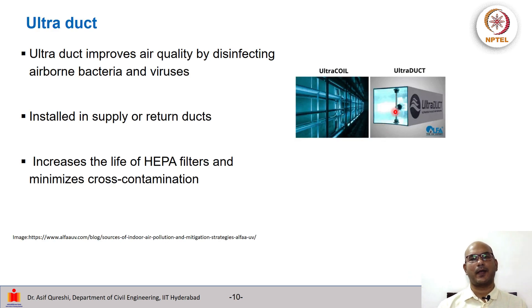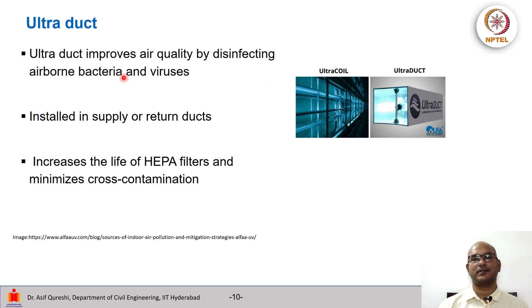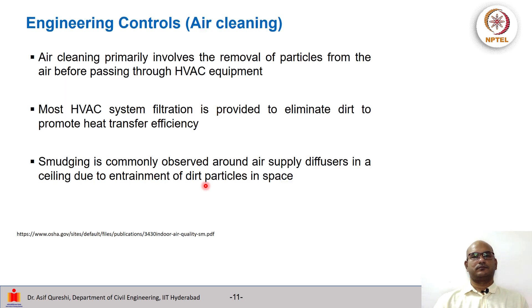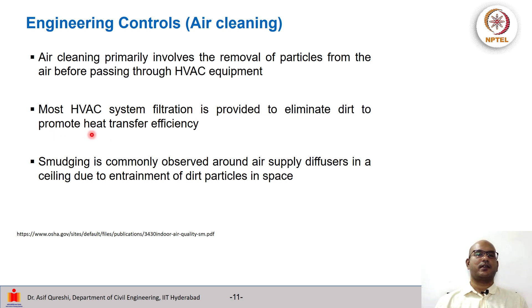Things such as UV ducts are being proposed. They improve air quality by disinfecting airborne bacteria and viruses and can be installed in the supply duct or the return duct. This increases the life of HEPA filters and also minimizes cross contamination. Some engineering controls also include air cleaning, which involves removal of particles from the air before passing through the HVAC equipment. For most such systems, filtration is provided to eliminate dirt and promote heat transfer efficiency. It is commonly observed that there is smudging around air supply diffusers in a ceiling due to entrainment of dirt particles in space.